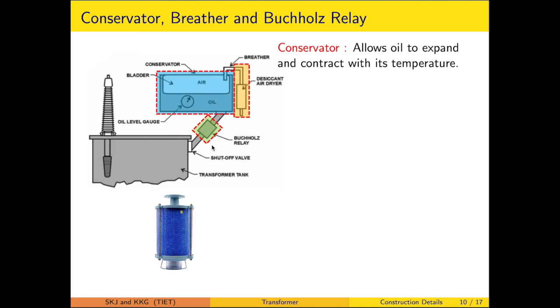So these particular parts are discussed here. The conservator is to allow oil to expand and contract with the temperature. The breather is to suck the moisture out of the air entering into the conservator. It is fitted with silica gel crystals, whose color changes from blue to pink after absorbing the moisture.